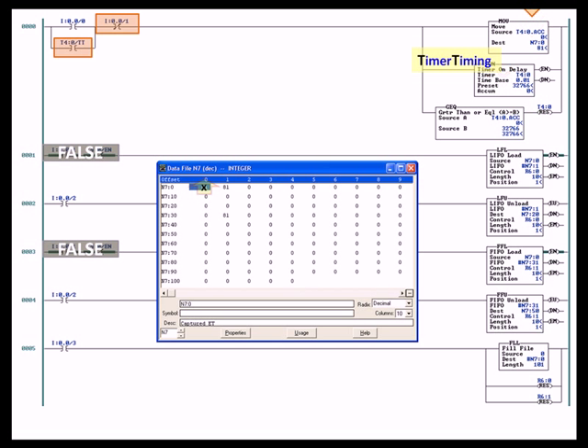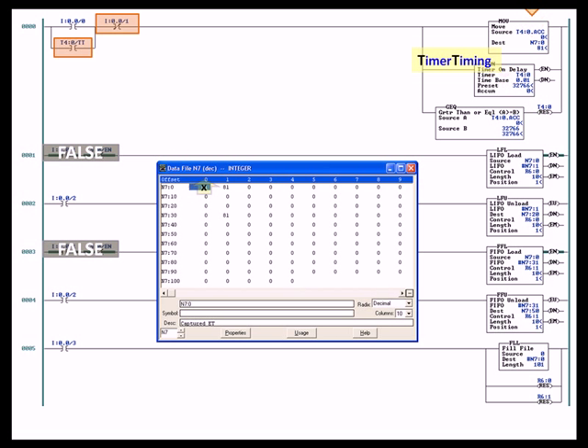Rungs 1, 2, 3, 4, and 5 are all false. Now the reason that I marked 1 and 3 the permissives false is because when I did the screen capture they were actually true, so I have temporarily put a little mask over them marking them as false. Because if you look at those two instructions, one of them is true if on for input 1. Well, input 1 is off right now, and that's what keeps the timer timing. If the timer is timing, then it's enabled, so the second instruction in rungs 1 and 3 would also be false.